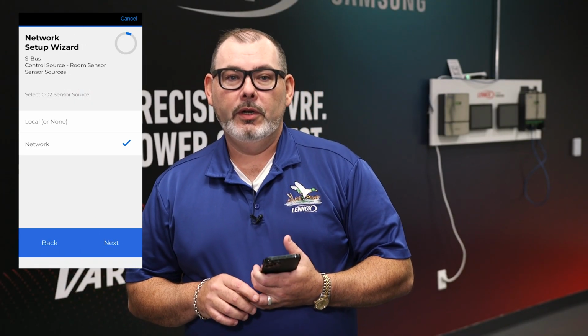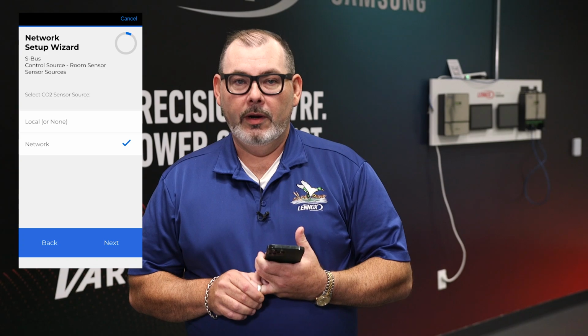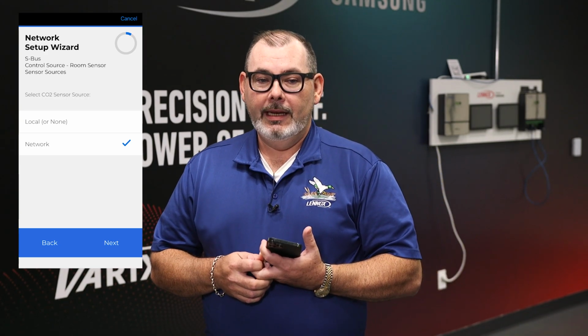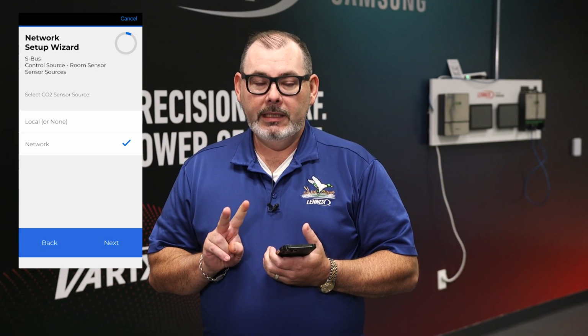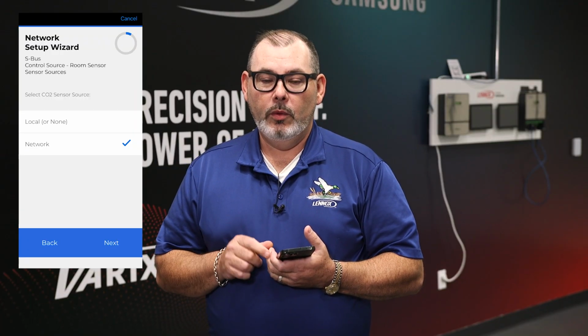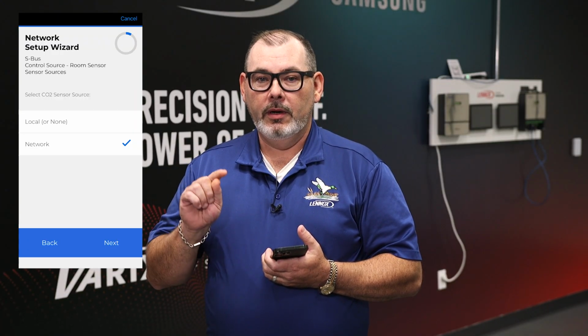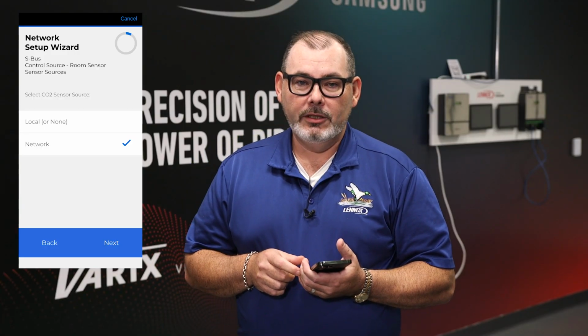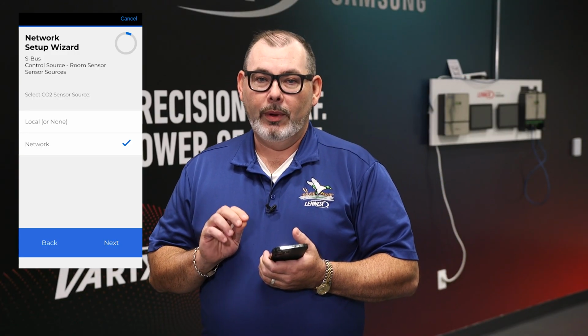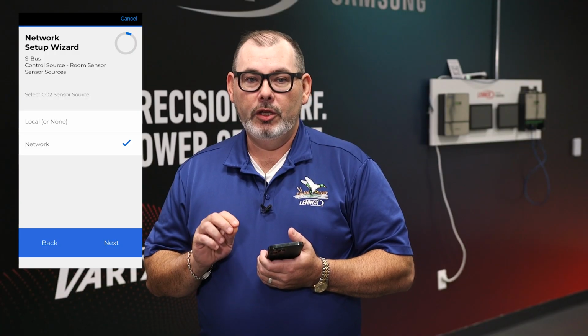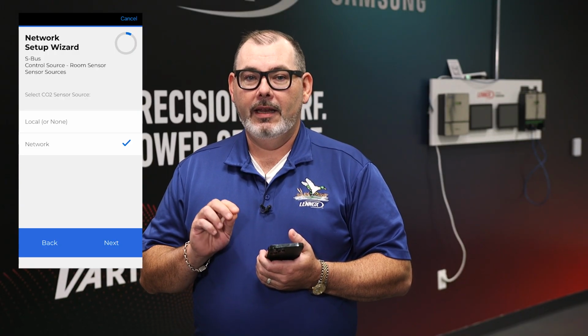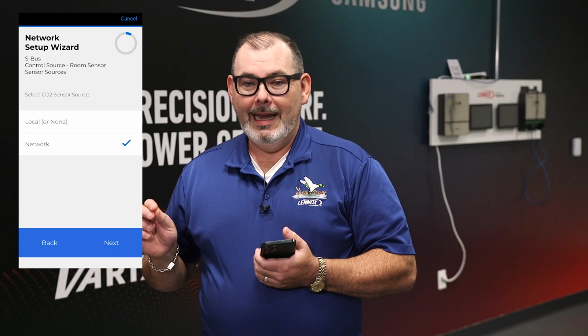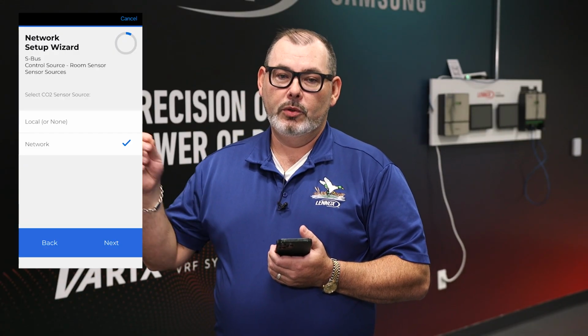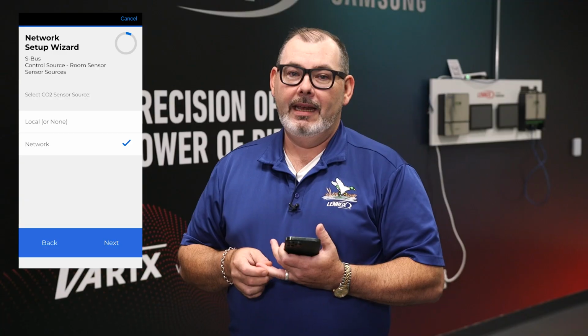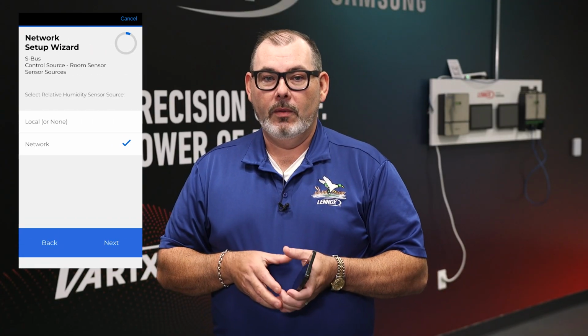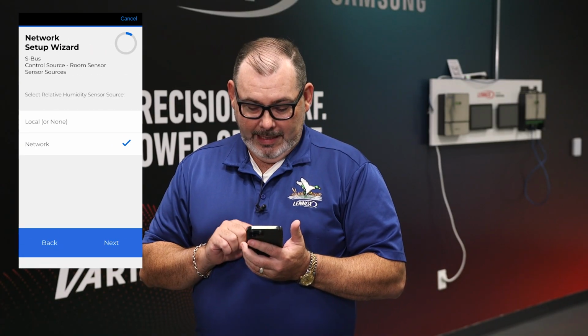This is going to prompt you for your CO2 settings for the controller. In the CO2 selection of setting up your CS8500, you will have basically 2 choices. One will be local or none if you don't have a remote sensor, and if you do have a remote sensor, it will come back to your core board and land on the brown connector that says IAQ. If this selection's not made, then you will need to make sure that your network is selected, because the sensor source will be coming from your CS8500. After you've made the correct selection for CO2, you will tap next.